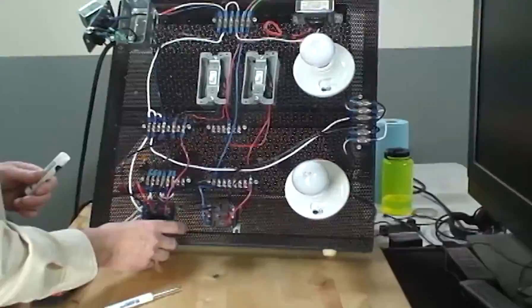Okay, remember I had L1 coming in here. Remember, here it is, L1 going back, go through fuse and all that stuff. Okay, now I'm going through the normally open set of points. And when you hear normally open, normally closed, what you're really saying is these are the way the points are arranged when there is no power on the relay coil. If I energize the coil, this point's going to close, that point's going to open, okay?